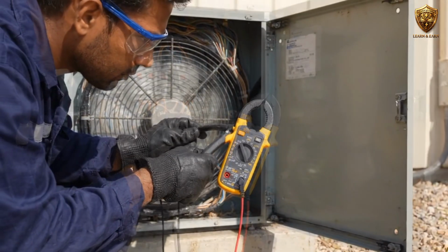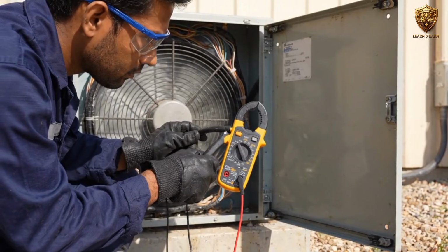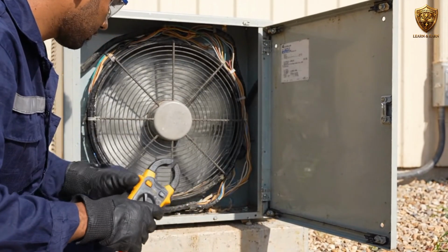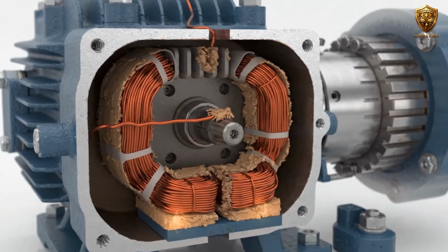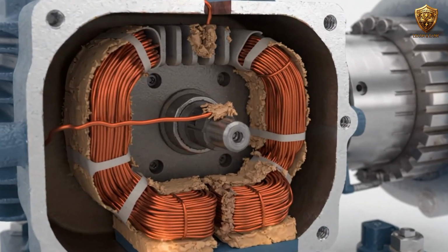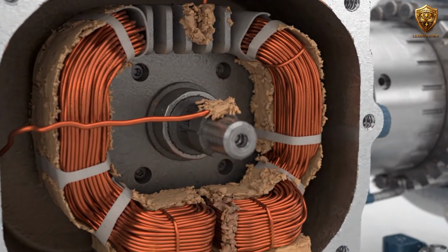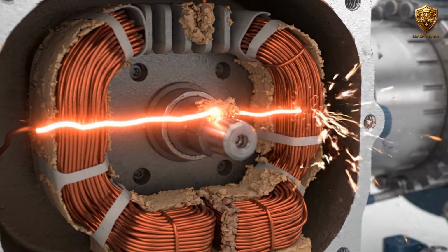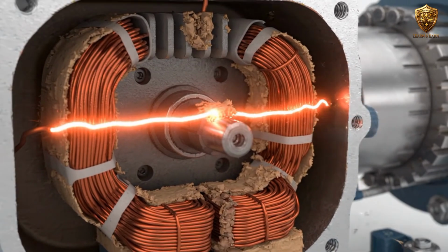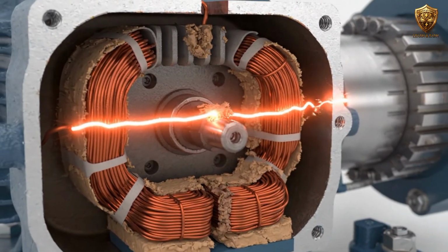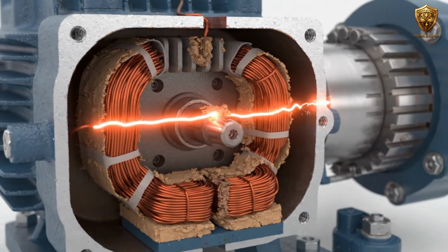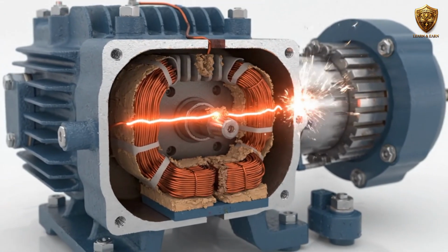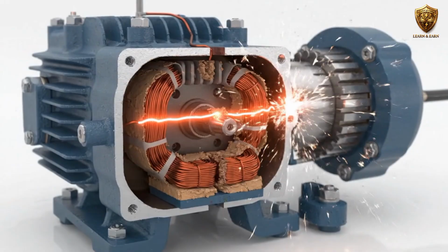A compressor that is locked mechanically can also show high starting current and may trip protection. But high current alone does not prove that the compressor is mechanically locked. Voltage conditions, system pressure, capacitor condition, and other factors must also be considered. This is where good troubleshooting becomes valuable. Replacing an expensive compressor without proving that it has failed can waste time and money. The same principle applies to other major components. Always test the cause before replacing the part.